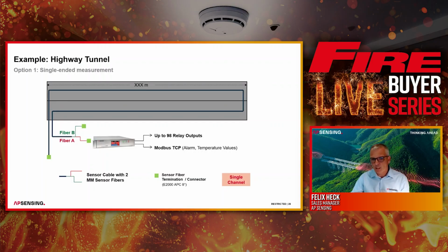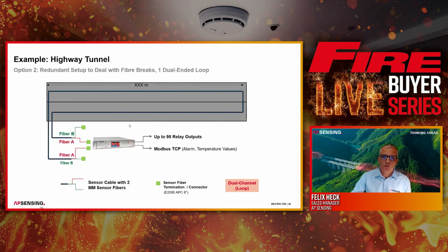We usually have the following one, with two channels on the controller, and the sensor cable will then be looped throughout the highway tunnel. The fiber optic will be connected to both channels in the controller, and the controller measures with the first channel through the highway tunnel, and then from the second channel backwards to the first channel connection here.